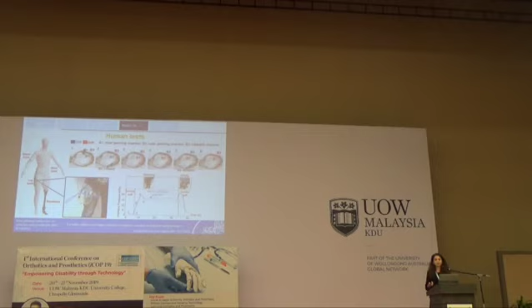By putting a Tekscan pressure sensor between the band and the limb, we tested the system starting from a soft configuration when the subject was standing. Then the system was activated, and you can see in the slide that it resulted in an increment of the pressure applied on the tissues, and so of the fitting of the system. Then, detecting the position of the subject by an accelerometer, when the subject switched from a standing position to a sitting one, the device was deactivated, became soft, and this resulted in pressure relief applied on the tissues.